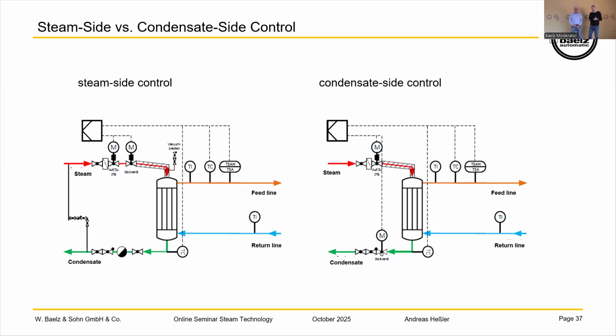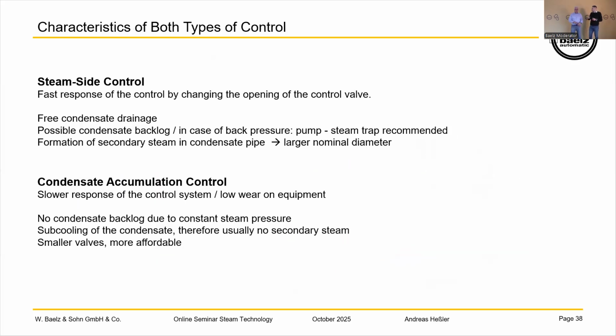On the other hand, we have the condensate side control, where we control the level of condensate in the heat exchanger. Let's do it with this slide. That's a good question. When we're doing the condensate control, in your words, your English is much better, we are controlling the condensate level inside the heat exchanger, making more or less heat exchanger area for the controlling. Correct. And you see it on this slide.